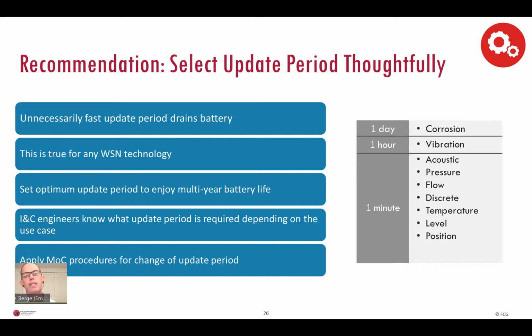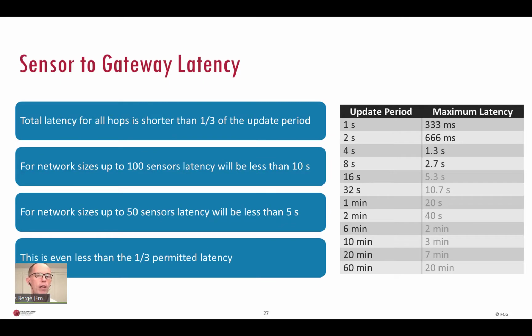Having said that, select the update period thoughtfully. Do not select an unnecessarily fast update period because it will drain the battery sooner. This is true for any wireless sensor network technology. Most wireless sensors are set to a 1 minute update period to enjoy multi-year battery life. Vibration may be set to 1 hour. Okay. Also, upload of large data sets like vibration spectrum or waveform should also be done thoughtfully.